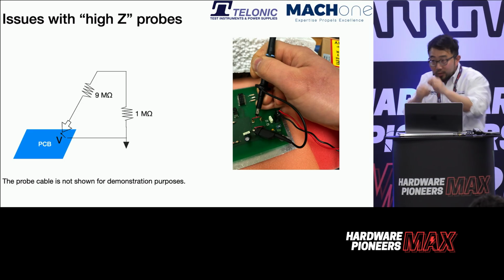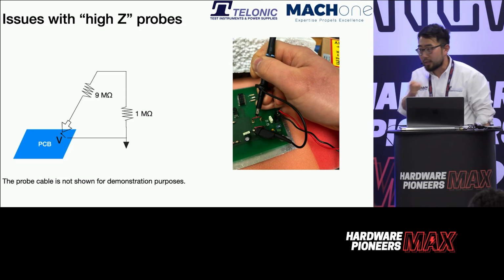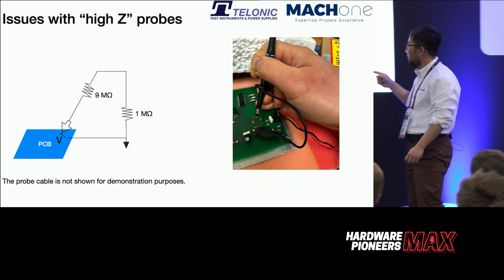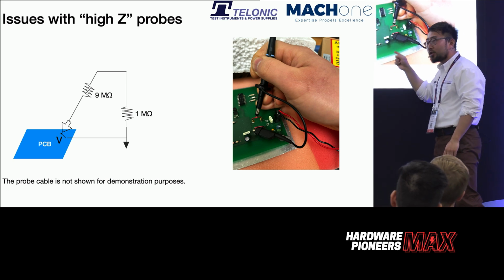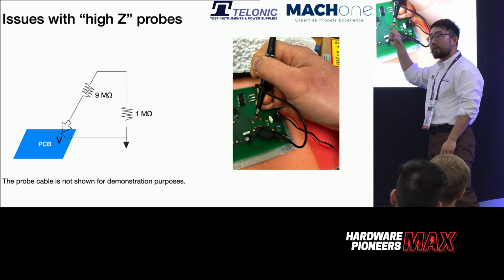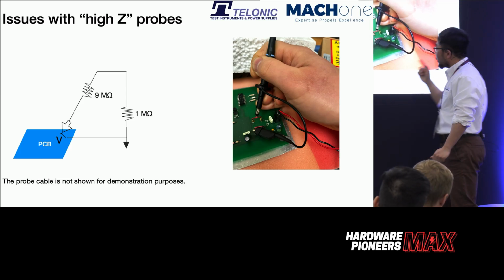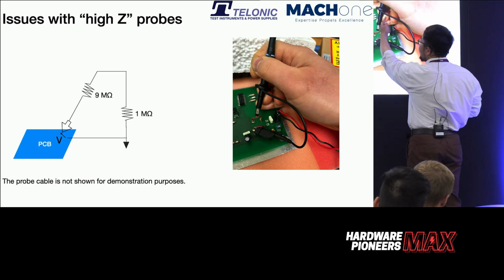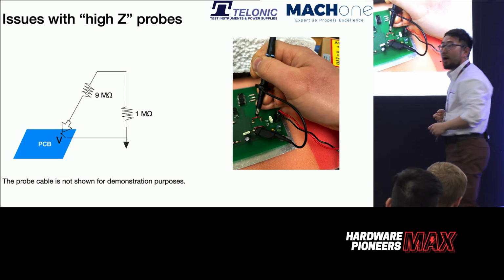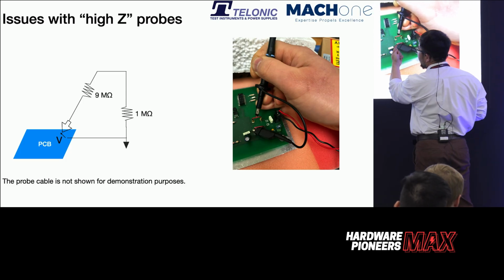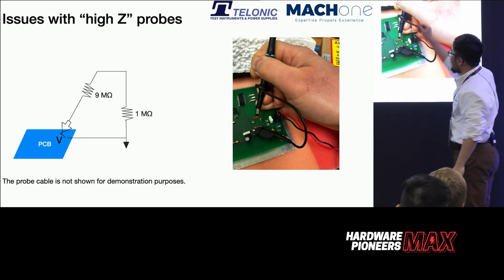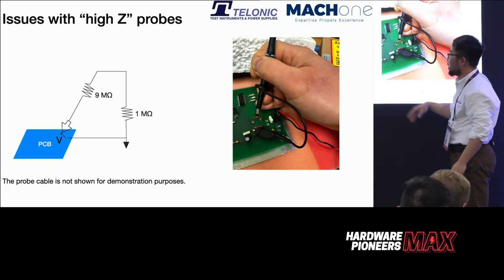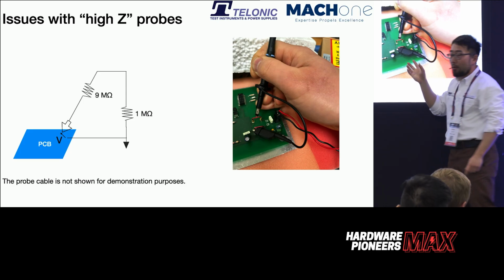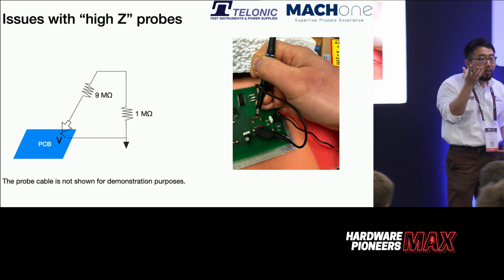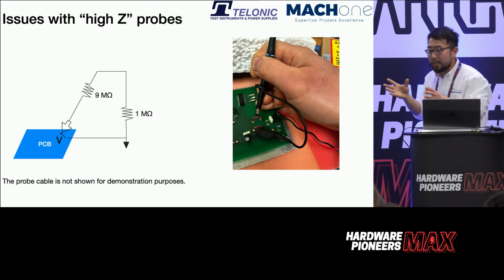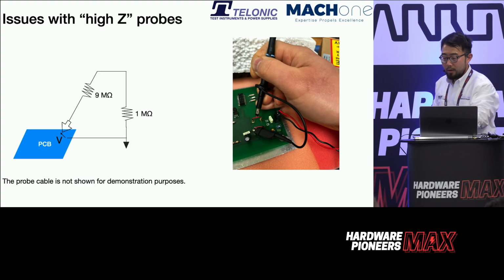I've seen signals, I've seen noise. But the question I'm going to ask is, are you 100% confident that the noise you're measuring actually comes from the measuring point you measure? Because this is what we call a loop antenna. If I short this ground pin to the tip and just put this here without touching the circuit, I possibly measure some noise. So the signal you are measuring perhaps is not really the true signal.